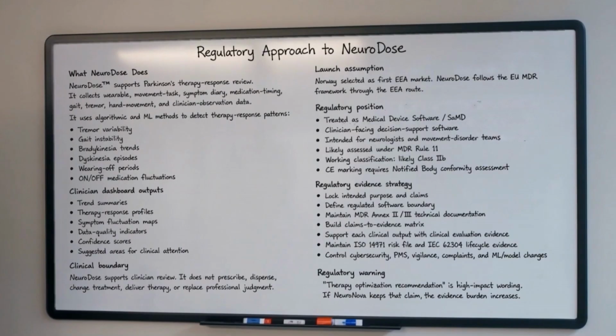Our initial launch focus is Norway. For Norway and the wider EEA, we are treating NeuroDose as software as a medical device under the European MDR framework. Based on the current intended use, the likely regulatory route is MDR Rule 11, with a working classification of Class 2B. This remains subject to the final wording of our claims and the outcome of the harm analysis. This route would require CE marking through a notified body, supported by Annex 2 and Annex 3 technical documentation.